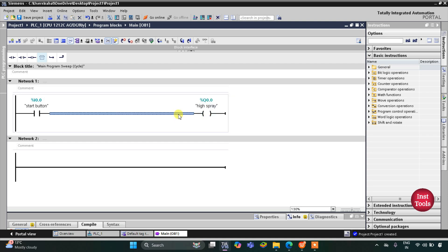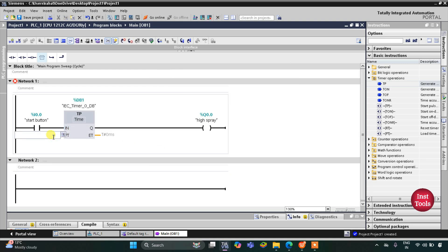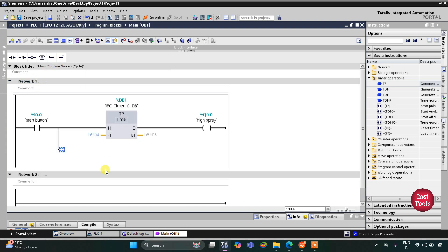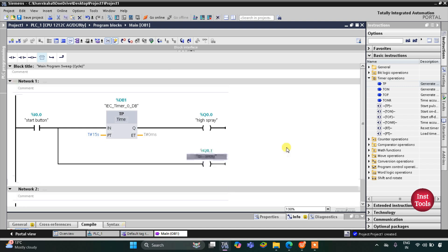This high spray will operate for 15 seconds, so I will use a timer operation — TP, the pulse timer. The preset value for this pulse timer will be 15 seconds. After that there will be a low spray, so I will open a branch here and insert a coil for low spray. This low spray will be after high spray, that means it will be after 15 seconds.